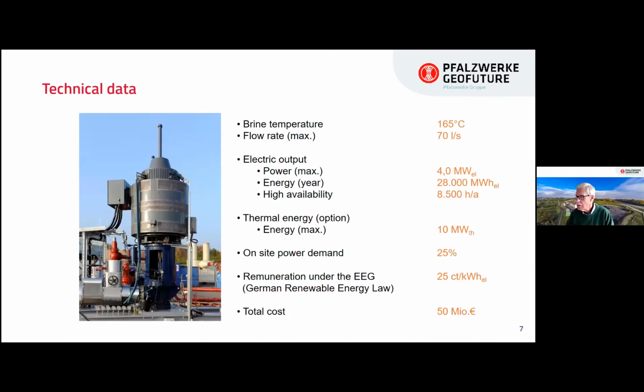Simona already showed our typical technical data. The brine temperature is around 165 degrees Celsius. Due to a not very promising reservoir situation, we cannot reach the intended 80 liters per second, which was the design basis for the whole project. We actually operate at between 65 and 70 liters per second. With this, we are able to generate 4 megawatts of electricity, thanks to a very high availability. The annual output is around 28 gigawatt hours of electricity.